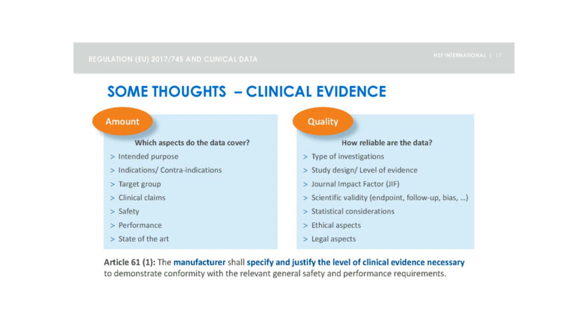And so on. In the end, the manufacturer has to specify and justify the level of clinical evidence necessary to demonstrate conformity of its device with the relevant general safety and performance requirements, as well as provide clinical data accordingly. The notified body will then evaluate the data and the manufacturer's justification.